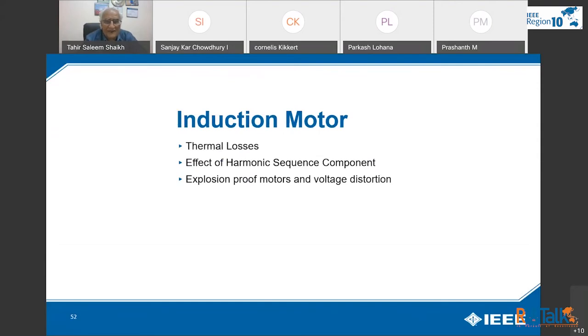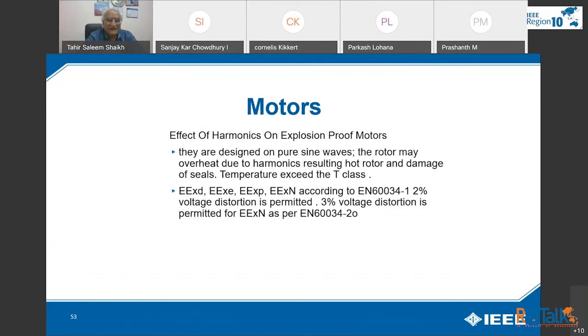Induction motor, again, in this the thermal losses will increase, with effects of harmonic sequence components, and voltage distortion. If you have an induction motor of a certain temperature classification, T1 to T6 are the classifications for hazardous areas, and you use it in such an environment where the temperature rises, this will destroy the seals of the motor, and the temperature classification will change and it will no longer be a hazardous area motor. So you can see here, explosion-proof motors are designed on a pure sine basis. The rotor may overheat due to harmonics, resulting in a hot rotor and damage of seals, and the temperature exceeds the T class.